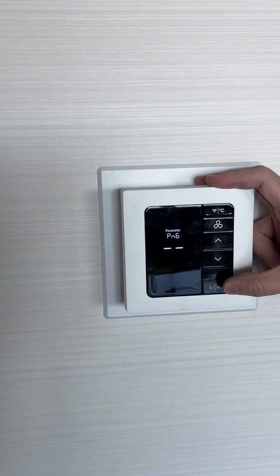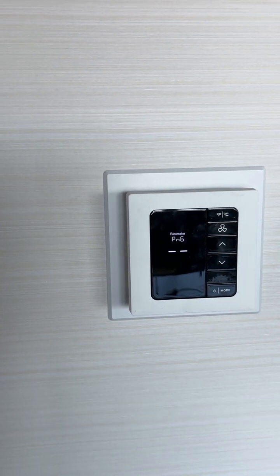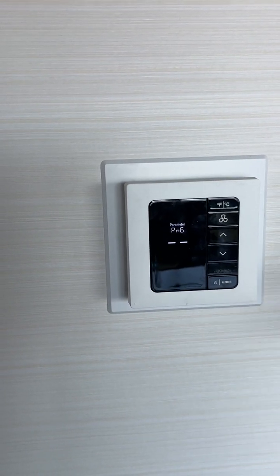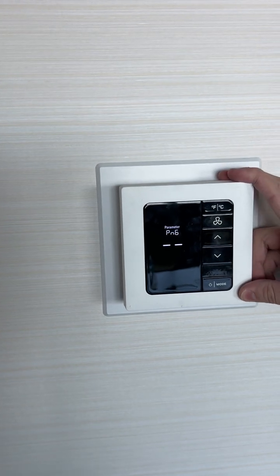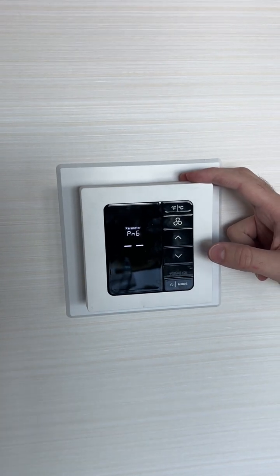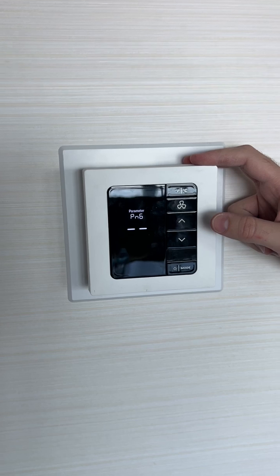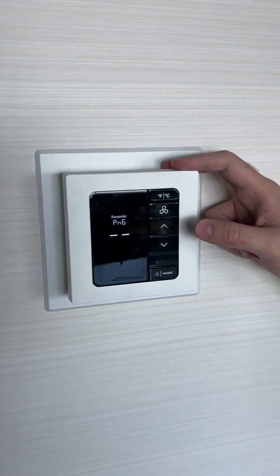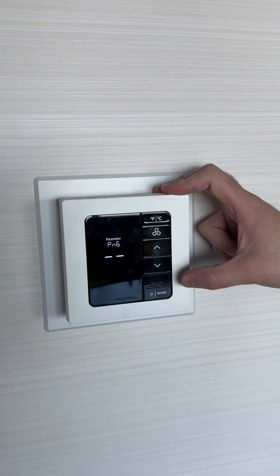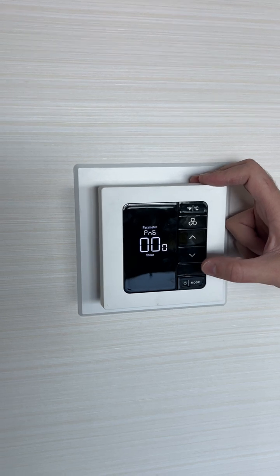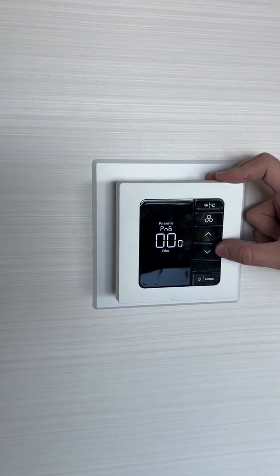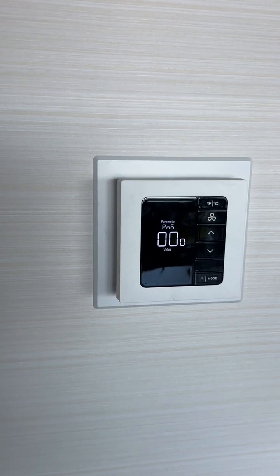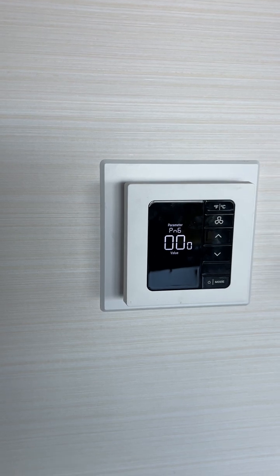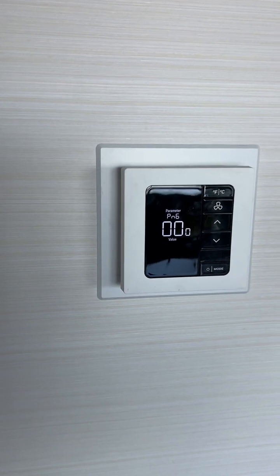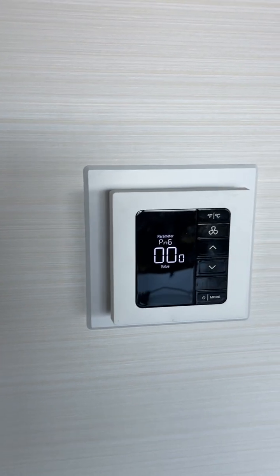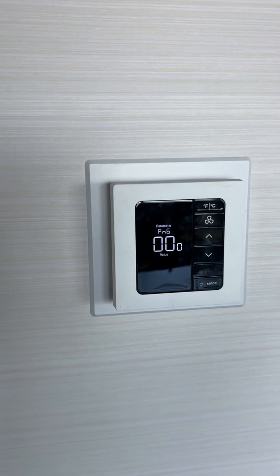PNG, or ping—this is where we can see what devices are communicating in the room. The commissioning document should state what address the devices are programmed as, as well as how it's shown here. So you go PNG, press enter. In a standard room, you'll only have 2 devices: the thermostat, which is address 14, and the X47, the relay pack in the unit, which is address 224.